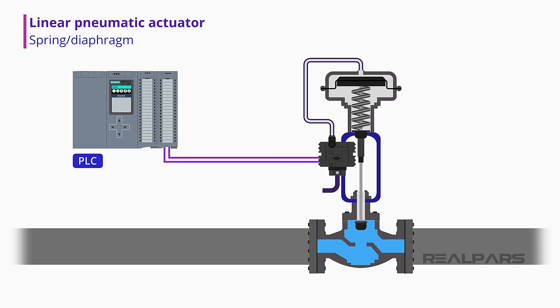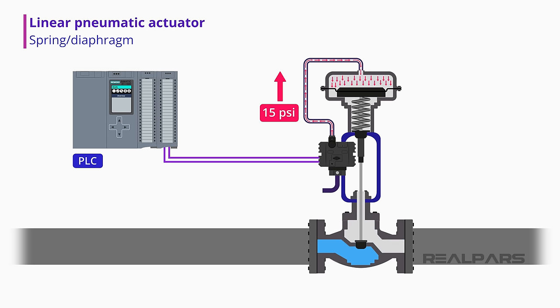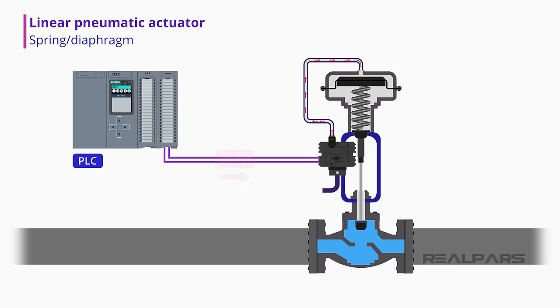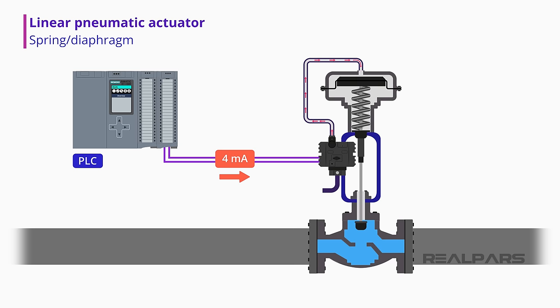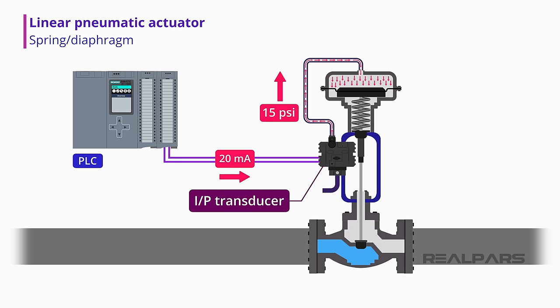Let's look at a typical spring diaphragm pneumatic actuator connected to a flow control valve in action. A typical pneumatic actuator will stroke a complete 0 to 100 percent over a pneumatic pressure input range of 3 to 15 psi. The PLC analog output card produces a 4 to 20 milliamp current to move the valve from fully open to fully closed. A signal conditioner called a current to pressure transducer, or I to P, will change the 4 to 20 milliamps into 3 to 15 psi.